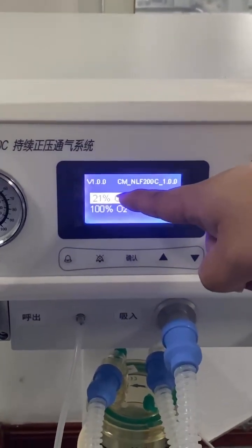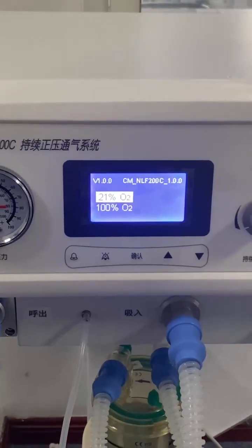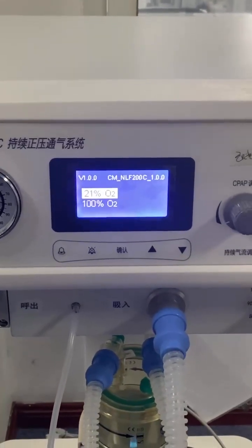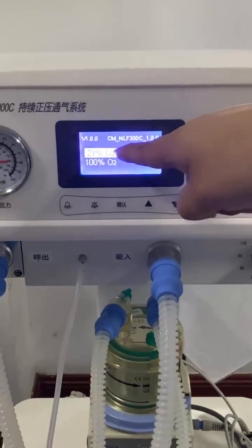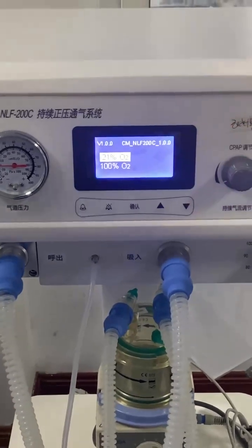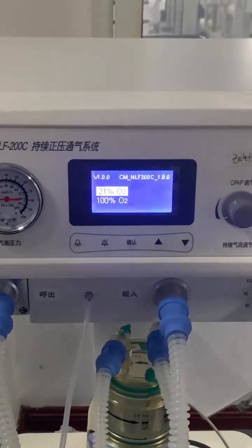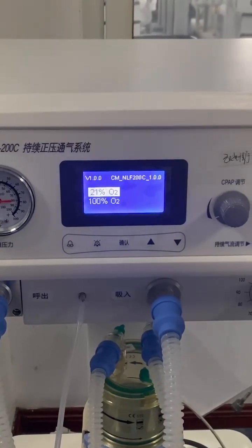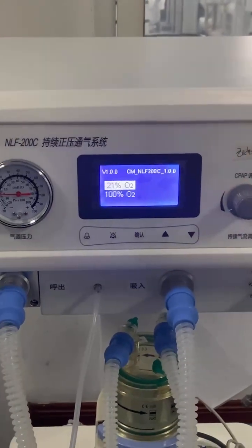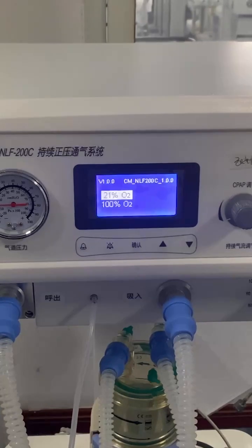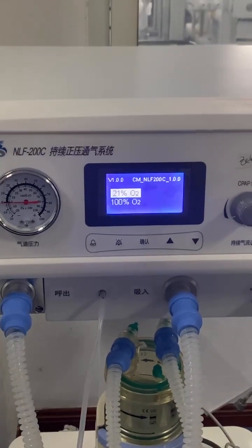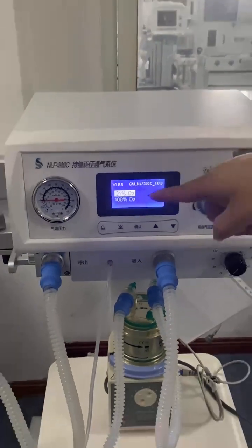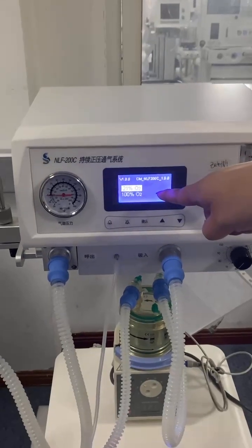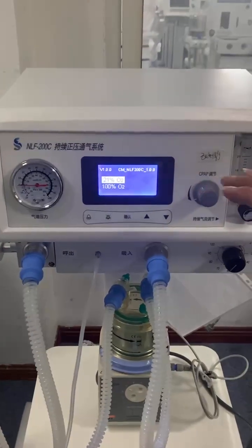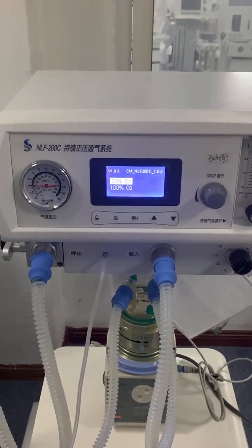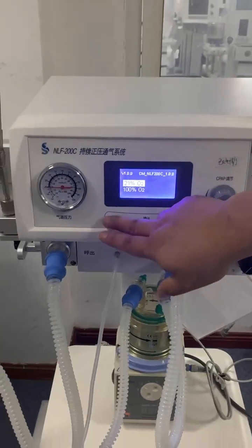So for the 21%, we will only ensure you are connecting with the air compressor without oxygen, and we press it. Then it will show complete after 10 to 20 seconds. And after the 21 point, we will do the calibration for the 100%. For the 100%, we will only connect with the pure oxygen and without any air compressor. So after 10 to 20 seconds, it will also show complete. After all of it shows complete, then the oxygen calibration will be finished. It's very easy.